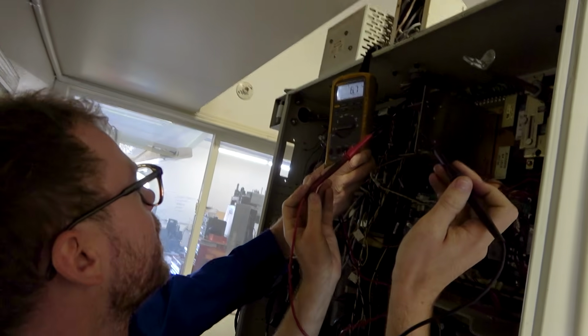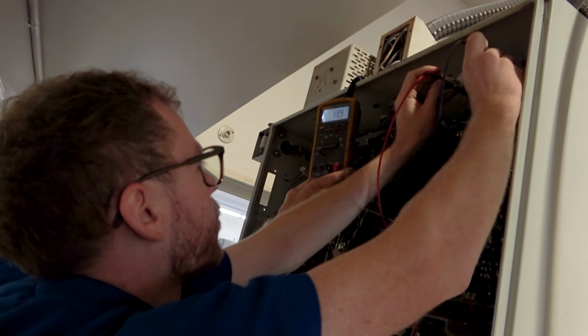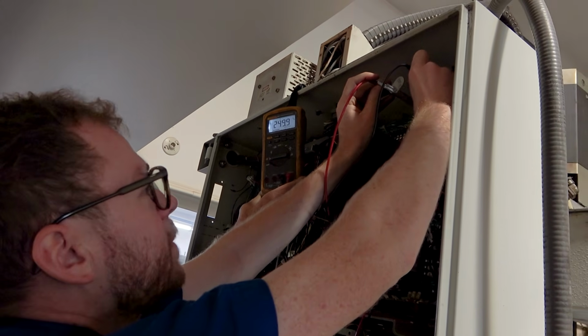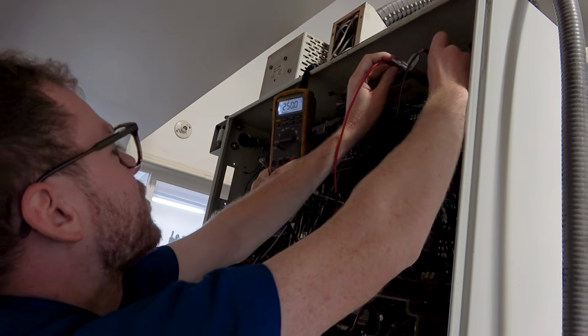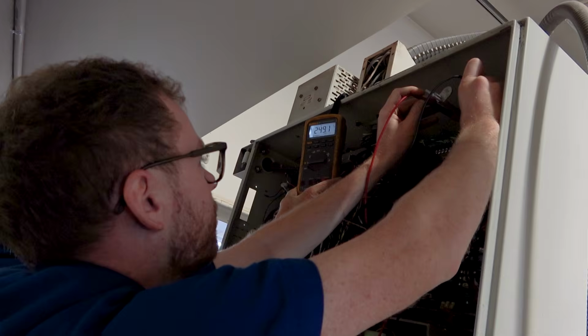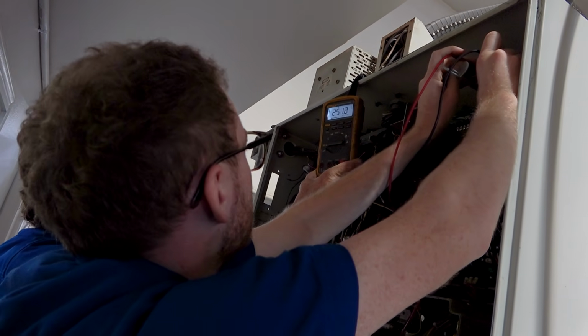So that's just randomness of me just touching things in the air. It can be confusing. You need to read on your meter what is the actual voltage. So I've got 250 between leg 1 and leg 2. I'm not measuring to ground. Then let's go from leg 1 to leg 3. 249. We take the third meter lead, and I'm going to put it over. 251. That was on the top.